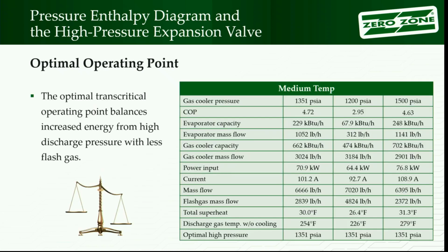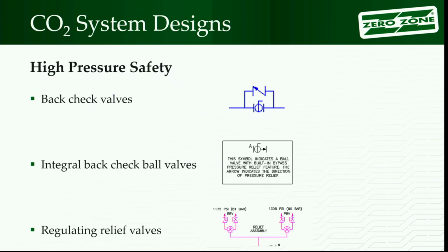A lot of the software out there does allow you to pick if you want to switch from optimal efficiency to maximum capacity. A lot of times they'll have a capability that lets you switch that. So if it's a hot day and you say, I don't care what the electric company says, they're complaining about the temperature, it'll switch over and start pushing that pressure up. It still has other safeties, right? Discharge pressure, discharge temperature, but it'll start moving that up.